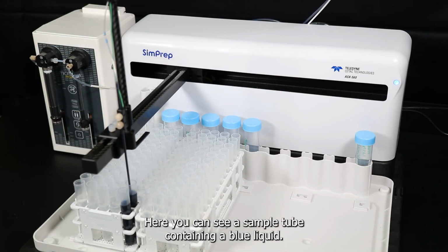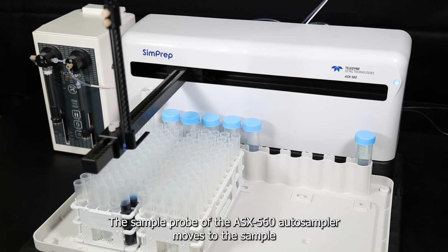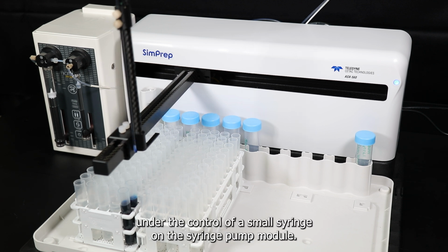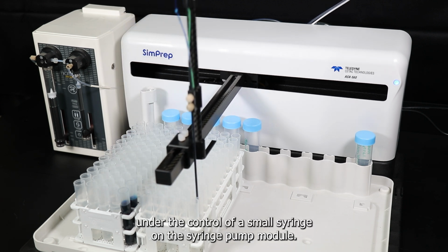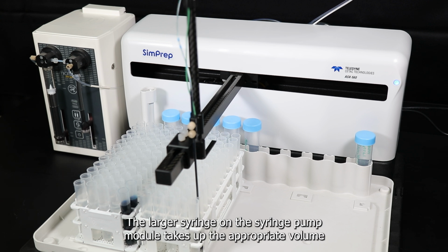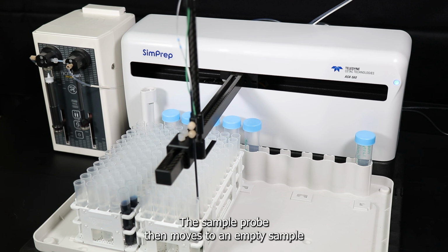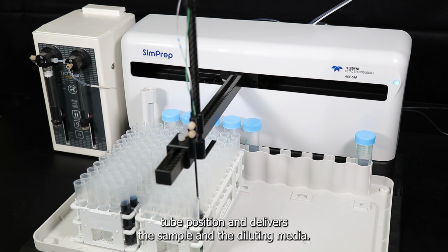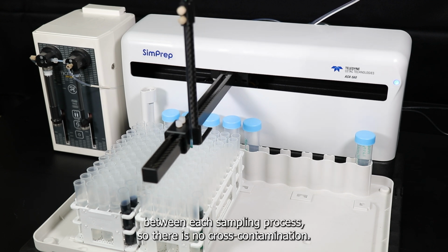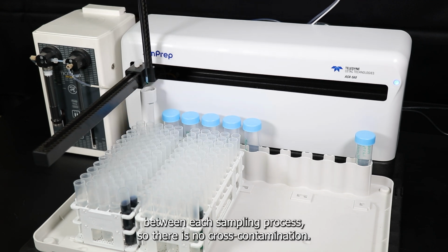Let's see this in action for a simple sample dilution. Here you can see a sample tube containing a blue liquid. The sample probe of the ASX 560 autosampler moves to the sample and takes up an aliquot under the control of a small syringe on the syringe pump module. The larger syringe on the syringe pump module takes up the appropriate volume of diluting media. The sample probe then moves to an empty sample tube position and delivers the sample and the diluting media. The sample probe is washed between each sampling process so there is no cross-contamination.